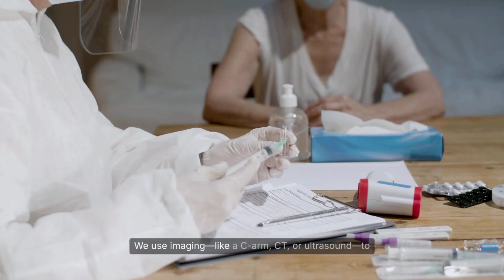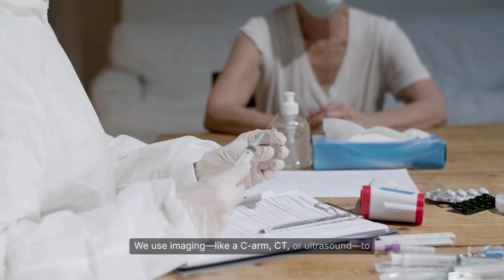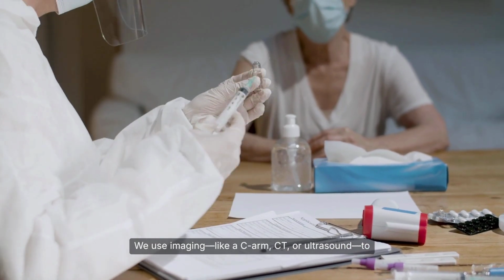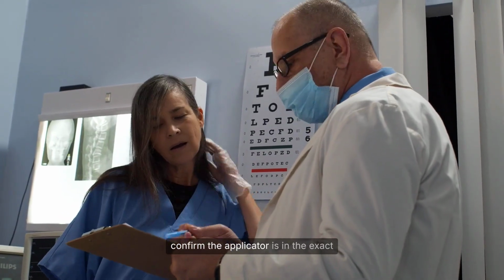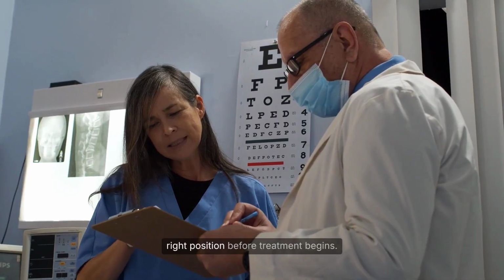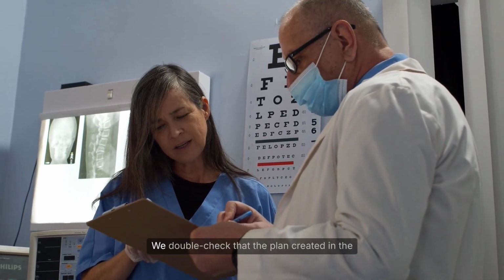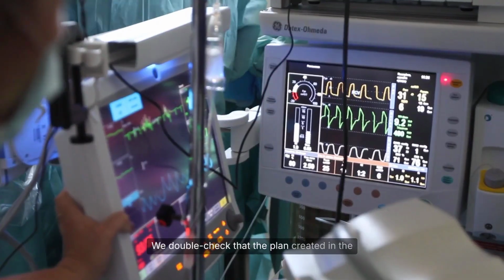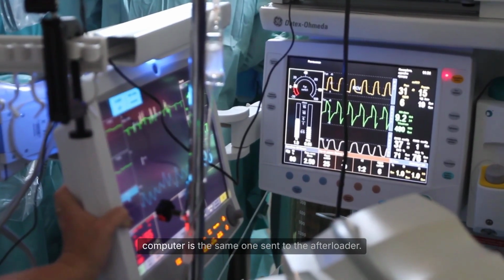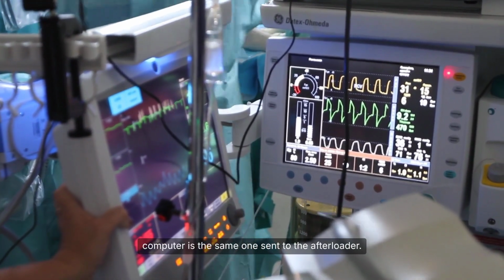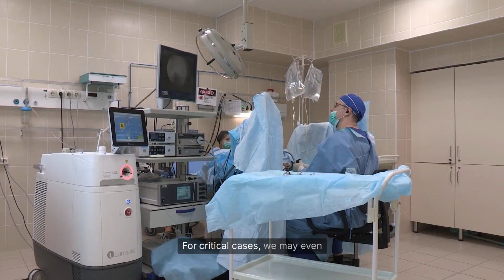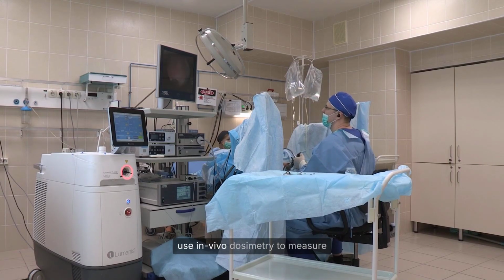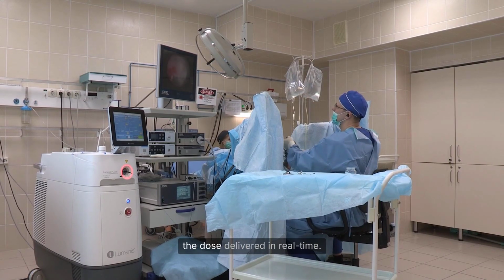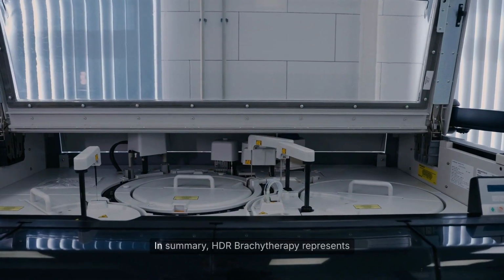We use imaging, like a C-arm, CT, or ultrasound, to confirm the applicator is in the exact right position before treatment begins. We double-check that the plan created in the computer is the same one sent to the afterloader. For critical cases, we may even use in vivo dosimetry to measure the dose delivered in real time.